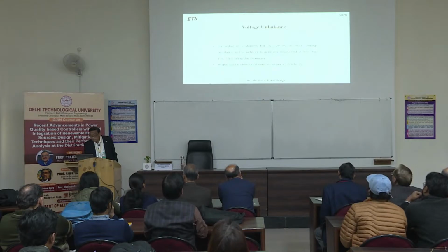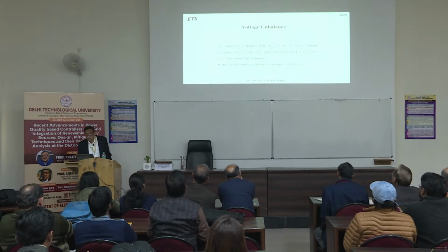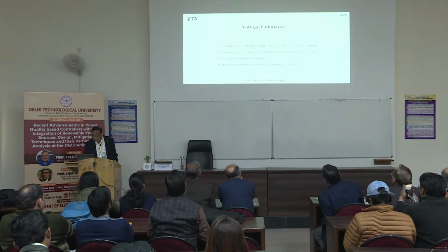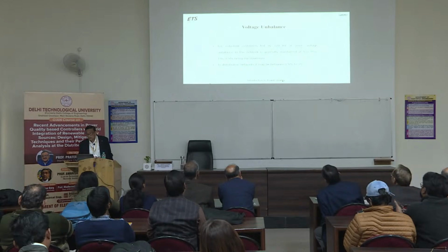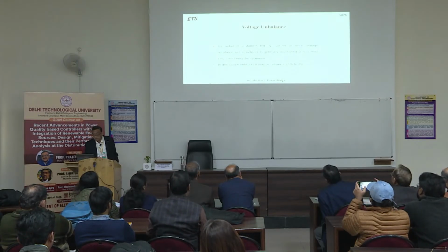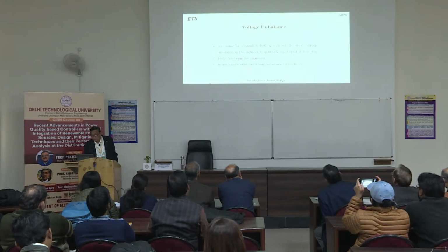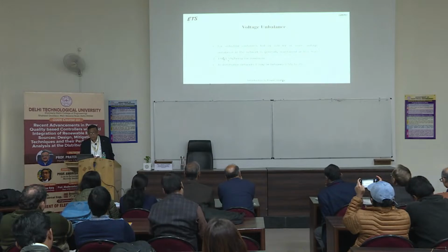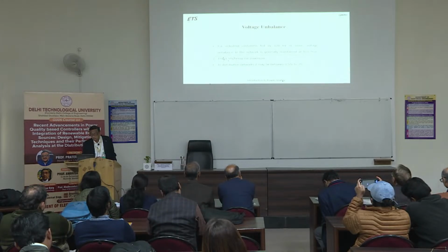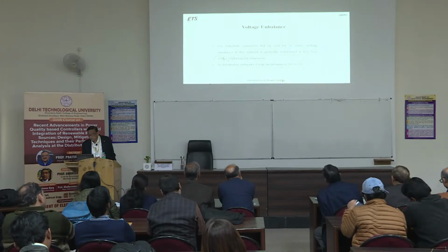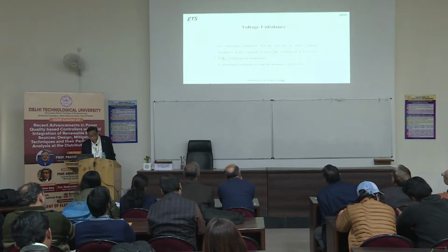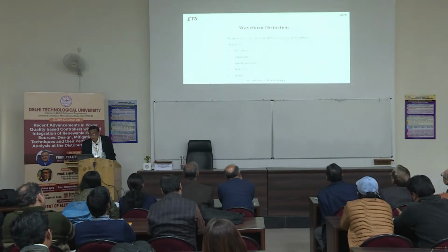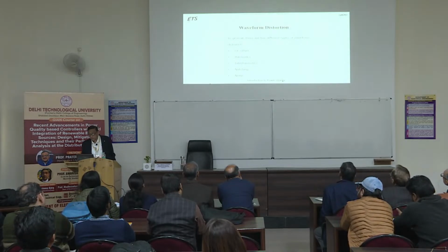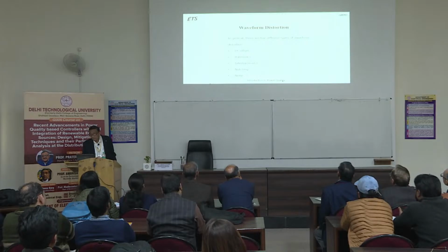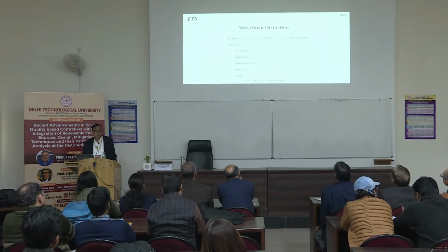For industrial customers fed by 120 kV or more, voltage unbalance in the network is generally maintained at less than 1%, or a maximum of 1.5% voltage unbalance. In a distribution network, it may be between 0.5 and 2%. Now the waveform distortion. There are 5 different types of waveform distortion.